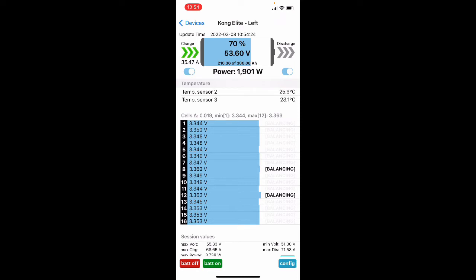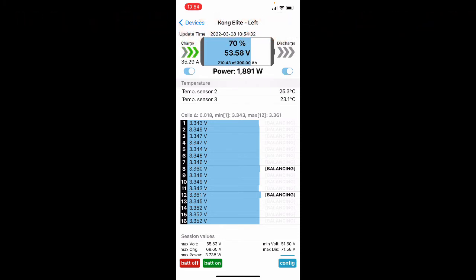I went from, I think, 2.28 volts per cell in the SMA - you multiply that by 24 to get the total voltage, since it's considering it a lead acid system, and lead acid systems are 24 cells in a 48 volt system. We've lowered that from 2.28 to 2.24, and that's what's giving us the 54.5 I showed you in the data from the Victron collection.